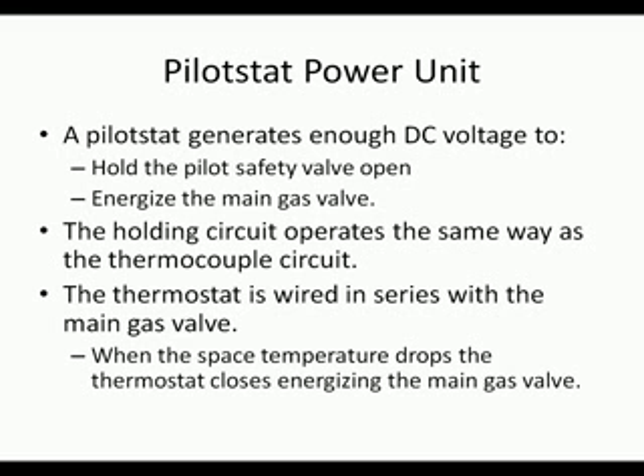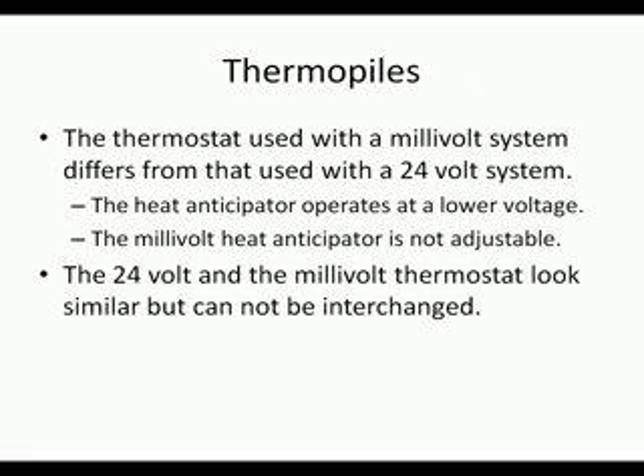The voltage output from a single thermocouple is 25 to 30 millivolts. 10 thermocouples in series, 250 to 300 millivolts. 25 thermocouples in series, 625 to 750 millivolts. A pilot stat is similar to a thermopile. It generates enough DC voltage to hold the pilot safety valve open and energize the main gas valve. The holding circuit operates the same way as the thermocouple circuit. The thermostat is wired in series with the main gas valve. When the space temperature drops, the thermostat closes and energizes the main valve.